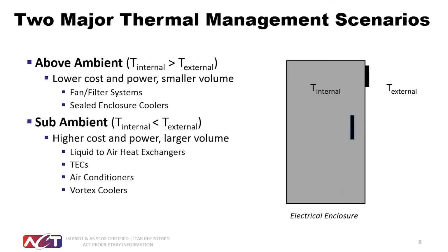Sub-ambient cooling is when the air temperature inside of the enclosure is cooled below the ambient temperature outside. Thermoelectric coolers and air conditioners are two examples of sub-ambient cooling equipment. In general, above ambient cooling solutions tend to have a smaller footprint and a lower cost than sub-ambient cooling solutions.